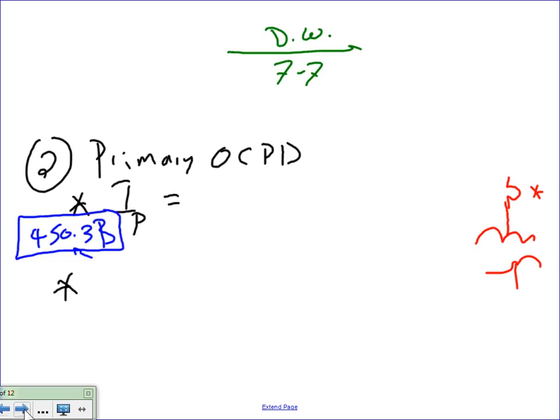If you don't have cut sheets for your transformers, everybody has 7-7. Can you guys look at that? 7-7 DeWalt. I am looking at 29.6 kVA. From 29.6 kVA, if you go to DeWalt, the first column gives you the standard industry kVA sizes of 3-phase transformers, right? So I have 29.6. What's my next standard kVA? Allowable 30, right? Everybody can see that? The next standard is 30 kVA.